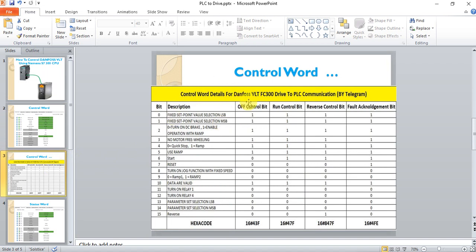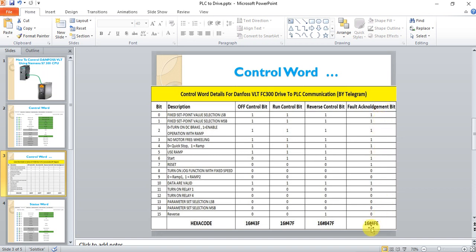This telegram is for the Danfoss VLT FC300. If I want to stop the drive, I will send the control word 043F. If I want to run the drive, I am going to send 847F. If I want to reset or acknowledge a fault, I will send 04FE.